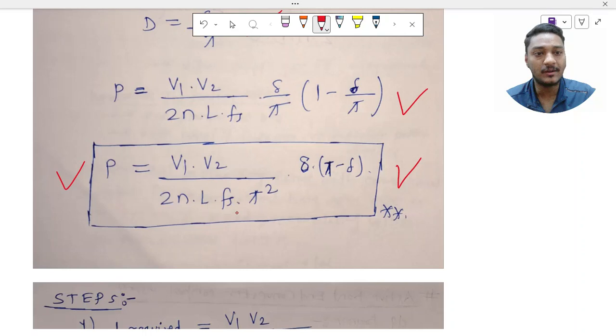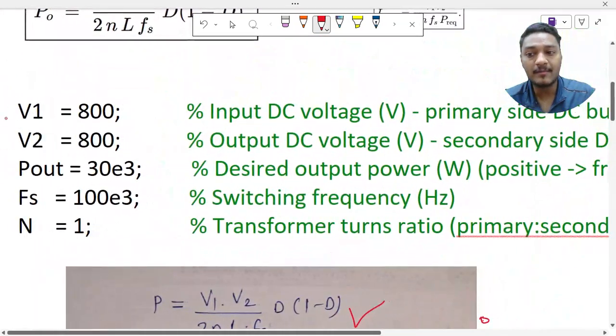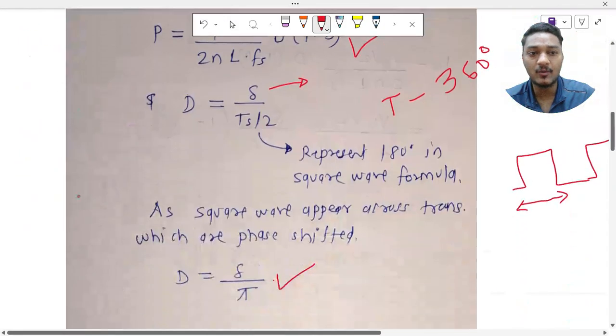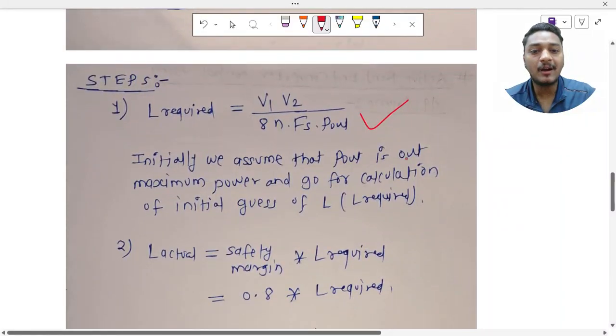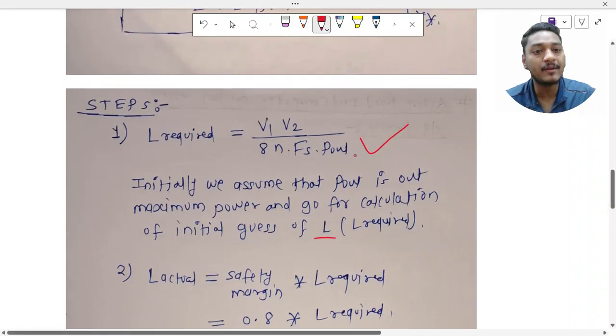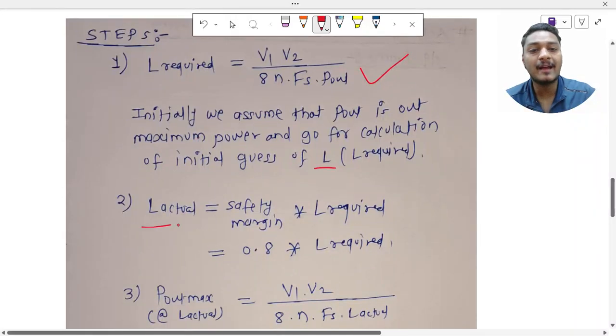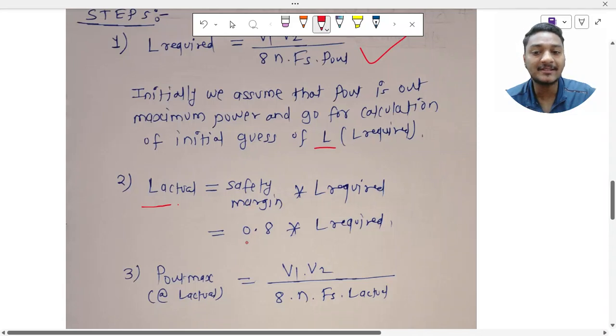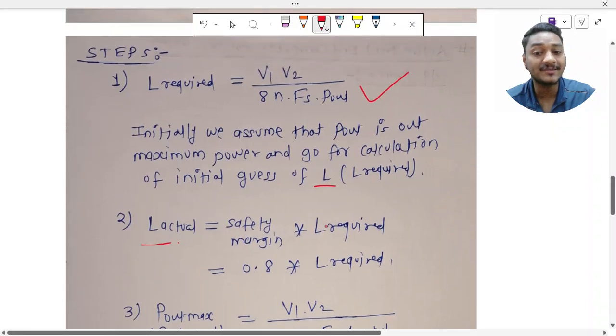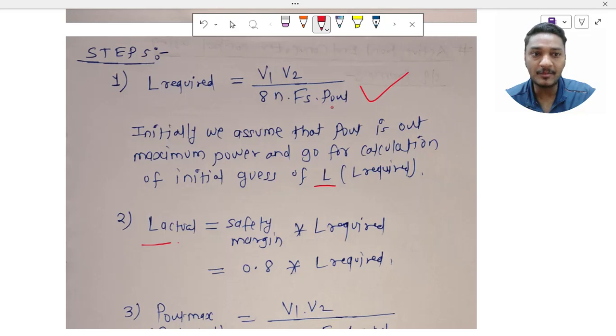To proceed, we know P_out, V1, V2, fs, and n. We first assume P_out is the maximum output power and calculate an initial guess for L: L_required is derived from the power formula with P = 30 kW by substituting V1, V2, n, fs, and P_out. Then L_actual is calculated by applying a safety margin factor of 0.7 or 0.8 multiplied by L_required.